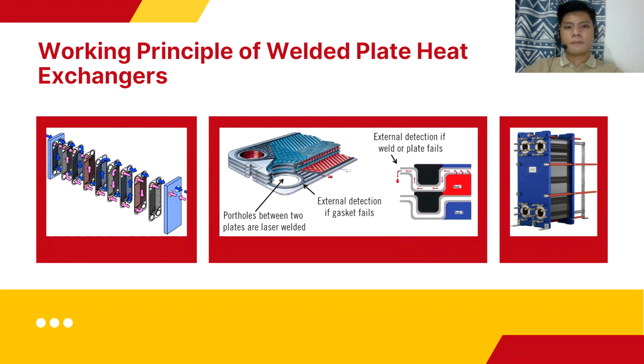This specific type of plate heat exchanger has its own working principle compared to other types of heat exchangers available in the market. The surface area of its wall, which separates the two fluids, is maximized, simultaneously minimizing the flow resistance of the medium. Channels are formed between the plates, and the corner ports are arranged so that the two fluids will flow through alternate channels. The cool fluid flows in an upward direction, and the fluid to be cooled flows in a downward direction, thus transferring heat through the plates for highest possible efficiency.